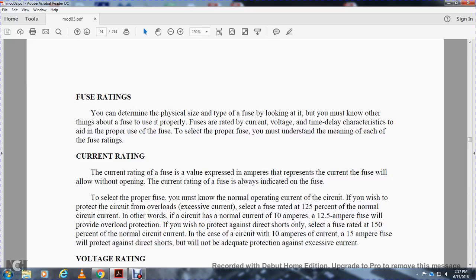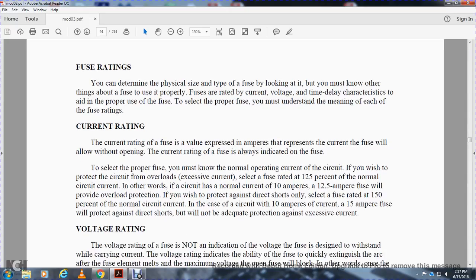In other words, for a circuit that normally carries 10 amperes, a 12.5 ampere fuse will provide overload protection. If you wish to protect against short circuits or direct shorts only, select a fuse with a higher current rating - for example, a larger ampere fuse that will protect against the direct short but will not be adequate protection against excessive current.